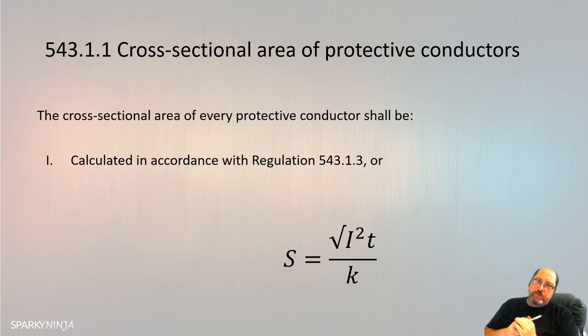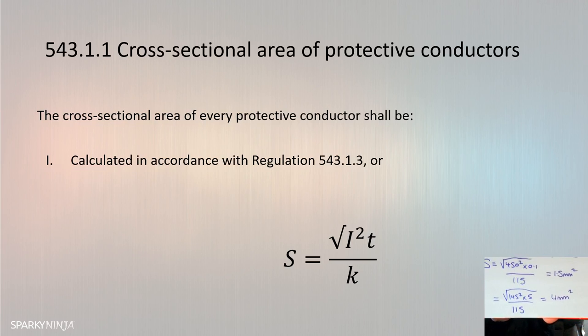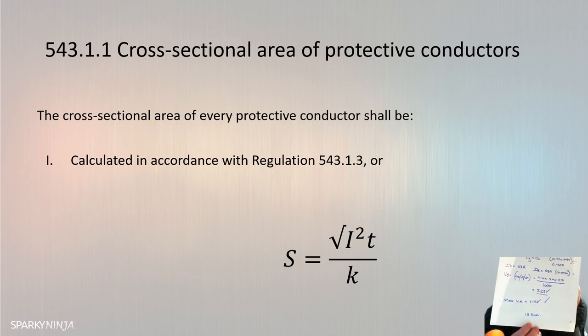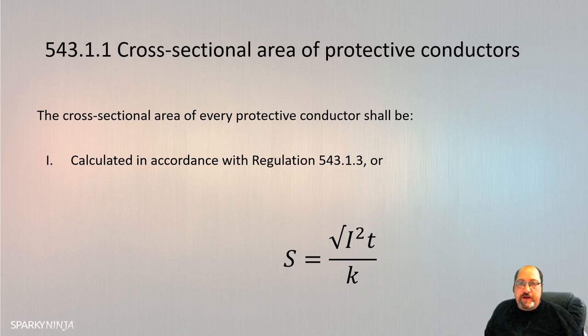So, my minimum protective conductor size, if my protective device is a 3036 with a maximum disconnection time of 5 seconds, which is the requirements of the regulations, changes from a 1.5 to a 4 mil. Okay. It was a 10 mil cable. So that's fine. But you can just see how changing the protective device can suddenly change the adiabatic equation and change the actual circuit's characteristics, sometimes for the worse, sometimes for the better.